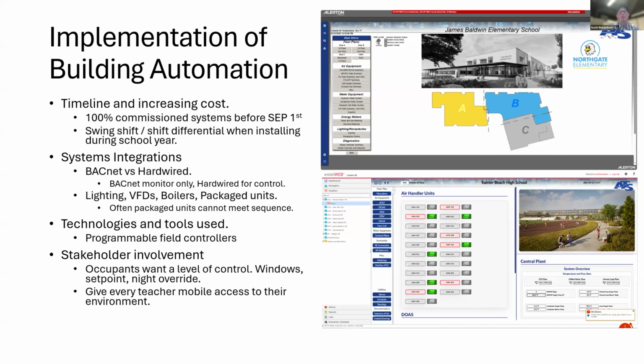So some of the tools that we'll use is a portable operating terminal to program these field controllers to make them operate to the sequence that is required. And the programmable field controller is your best bet. You don't want your sequence to be managed by your front end. You want all of your fine-tuned sequences to be on the local level in the controller that's touching the pieces of the field hardware that's attached to that unit. If you have it on the front end, of course, any communication blip is going to make you dead in the water, like all those sci-fi movies when the mothership dies, all the drones die.